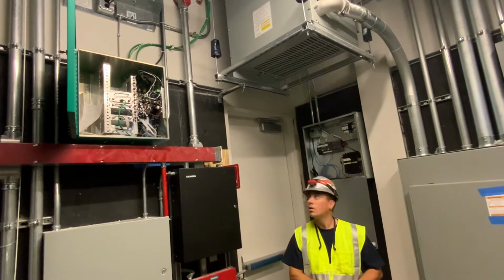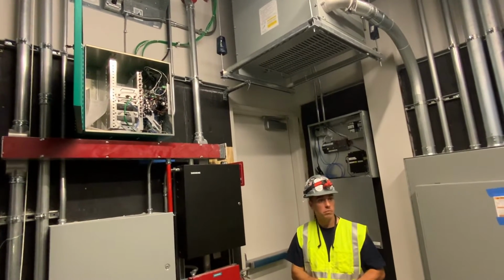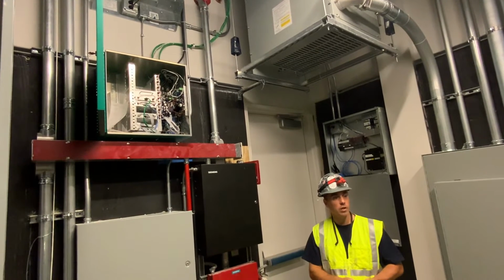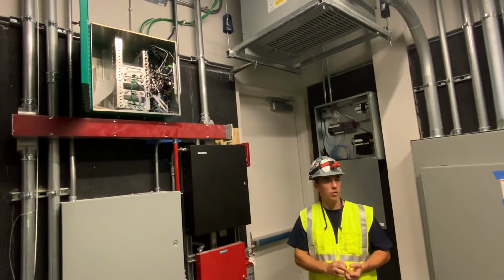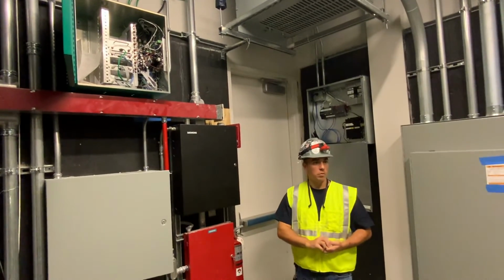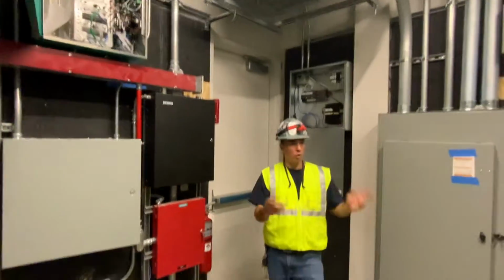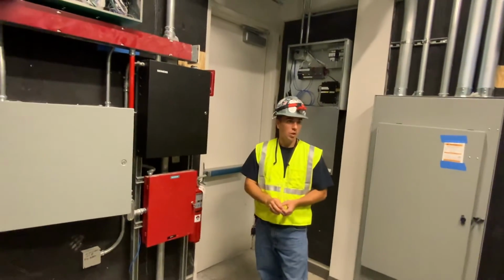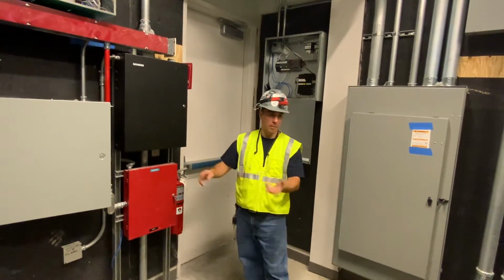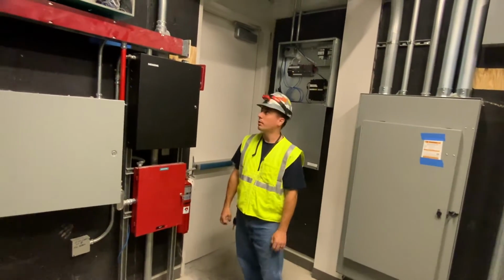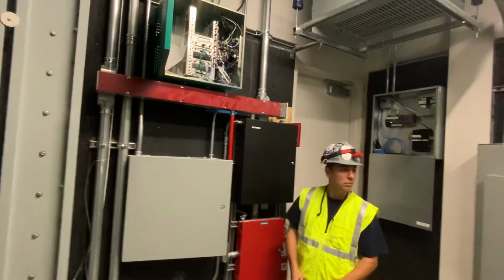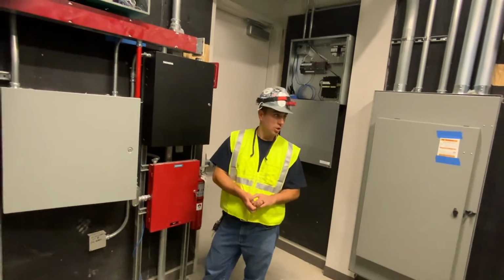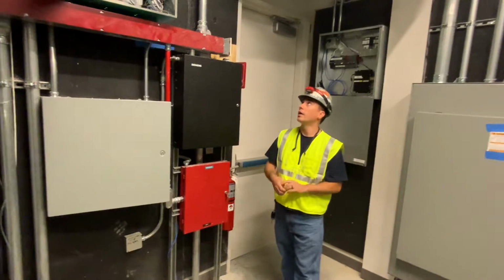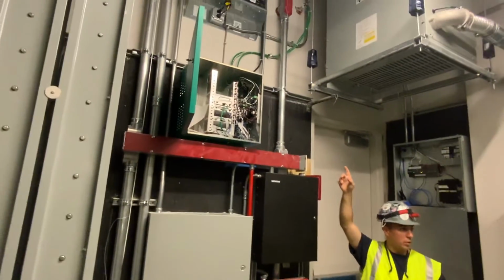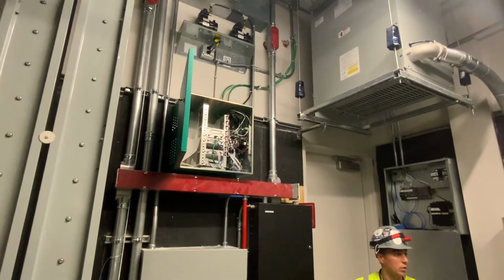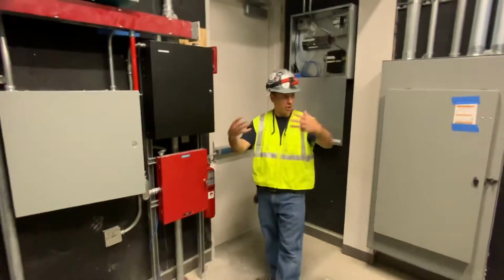Right, okay. Is there regular maintenance that needs to be done on this? There's nothing that you need to do with this. So that's all the contract, I don't know what it is with Drexel, but it's either a contract with TKO or with AIRCUITY, and then we're sub to AIRCUITY. So if there's ever an issue with this, you call us and we come out and take care of it. Well, you come here yearly? We come here twice a year anyway, to change out the sensors. If there's a failed pump, we are not recalibrating, I'm just putting in a new calibrated sensor. So I don't do the calibration here, they ship out calibrated sensors.